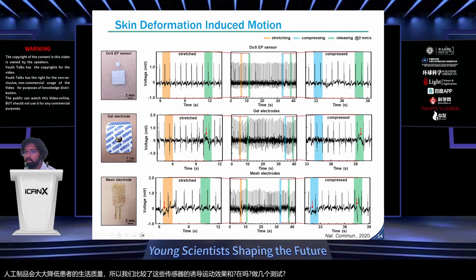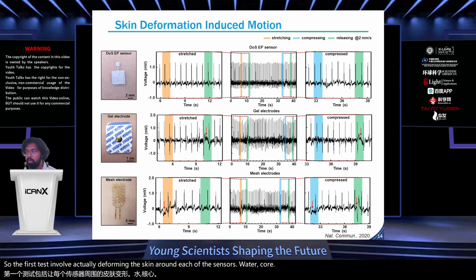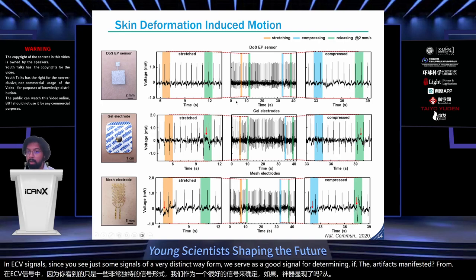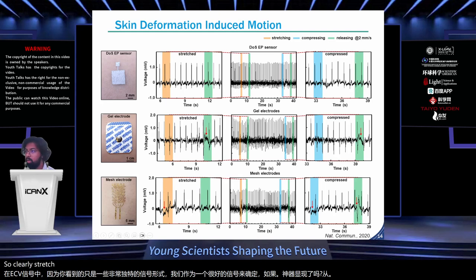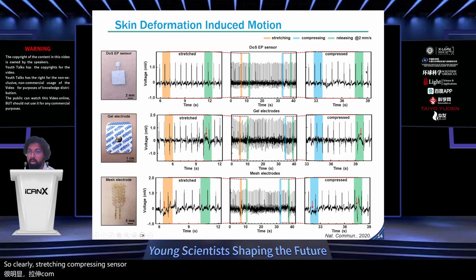The first test involved deforming the skin around the sensors while recording signals. Since ECG signals have a very distinct waveform, they serve as a good signal for determining if an artifact is manifested from motion. Clearly, stretching, pressing the sensor, and releasing the deformation had no effect on the ECG waveform recorded with the DOS sensors, whereas the others were clearly affected.